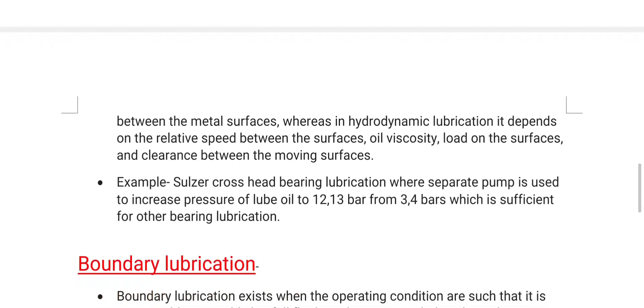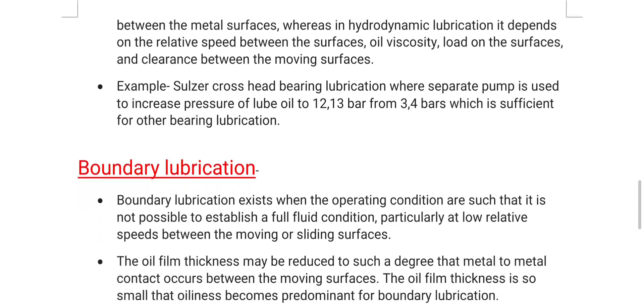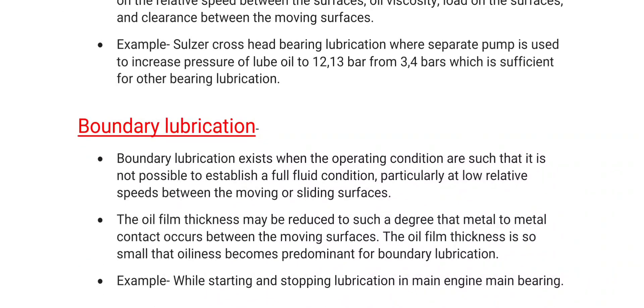An example of hydrostatic lubrication is the slow-speed crosshead bearing lubrication, where a separate pump is used to increase the pressure of lube oil to 12 to 13 bar from the normal 3 to 4 bar, which is sufficient for other bearing lubrication. The third type of lubrication is boundary lubrication.